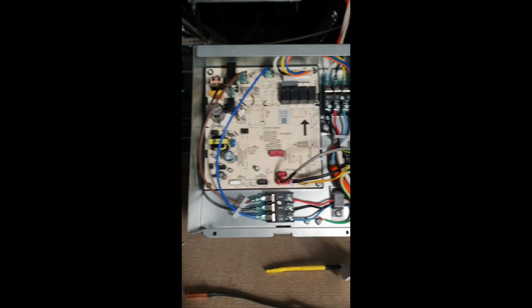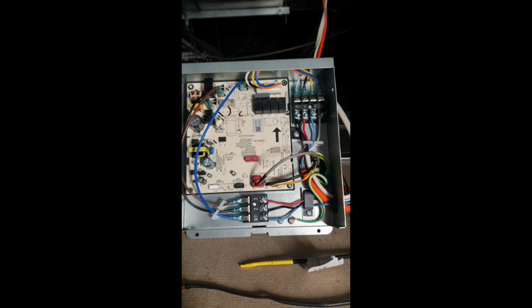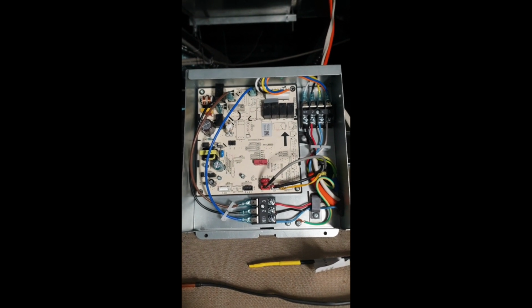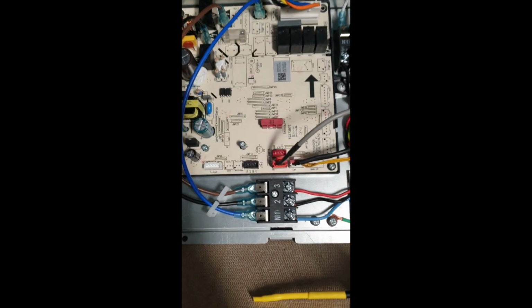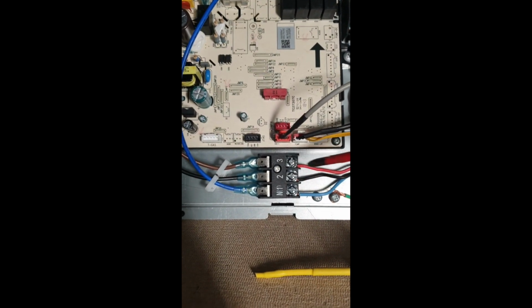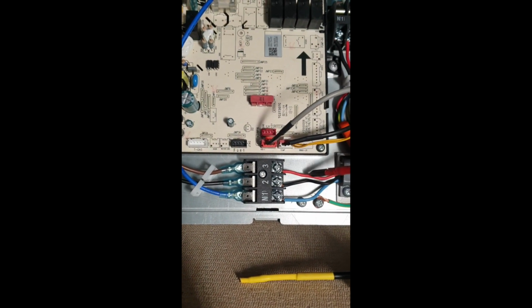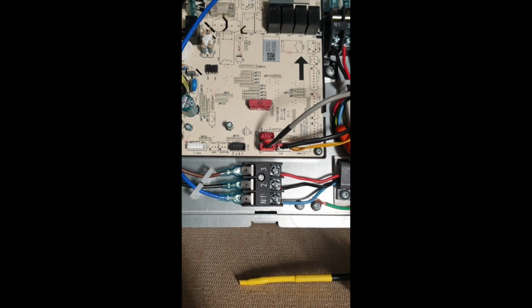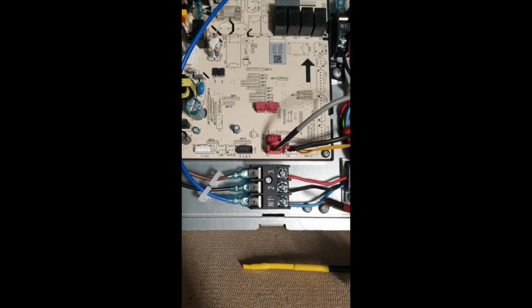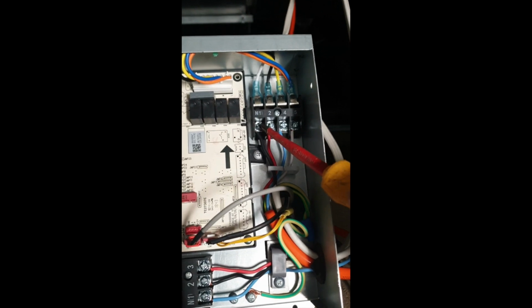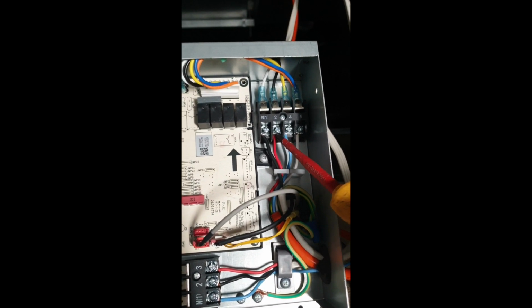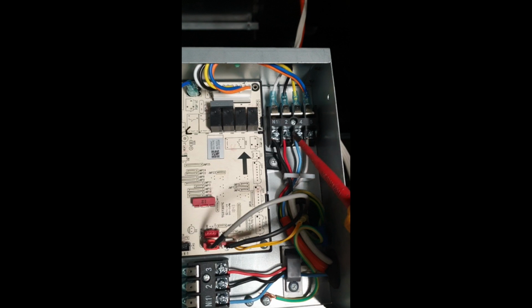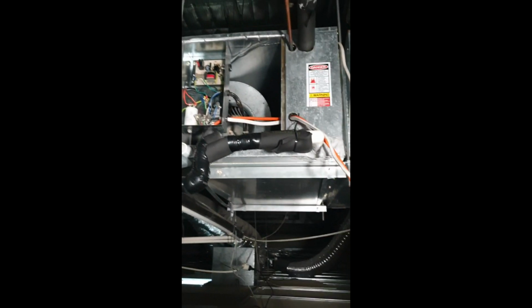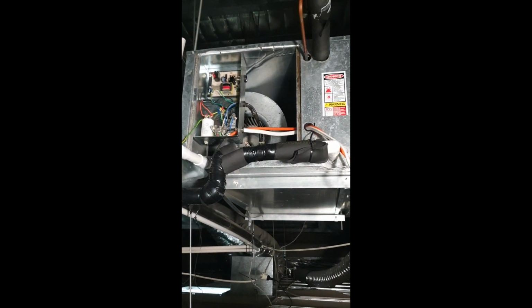We are looking now at the very simple electrical component, the board that comes with the Intelligent Series. For starters, the bottom terminal block is showing neutral, active and communications coming from the outdoor unit. It's that simple, so that's on the bottom of this panel. So active, neutral and comms back to the unit. The top strip is nothing other than neutral and the 3 fan speeds for the indoor motor. This indoor motor, as we can see, is a pretty old machine. It's in good condition, must be 240 volt.